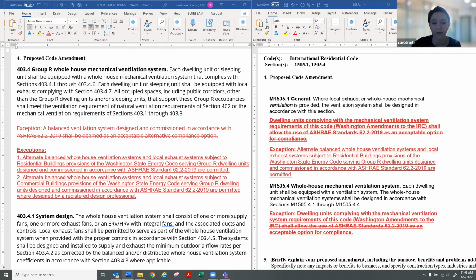Thanks, Nancy. Mike, you put something in the chat. Do you want to speak to that? Sure. The 2024 IMC has been updated to align the ventilation rates with ASHRAE 62.2. So if you guys are looking to address that in particular, and ensure that the ventilation rates are more commensurate with what 62.2 requires, you can just skip the 62.2 reference and then just modify the floor rate coefficient for the ventilation rate equation from 0.01 to 0.03. And that should probably do what I'm hearing you guys wanting to do here, unless I'm misunderstanding.